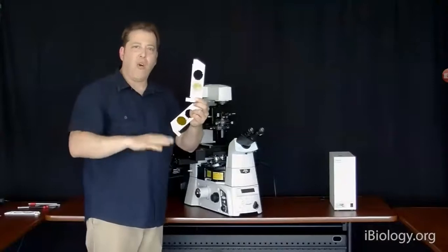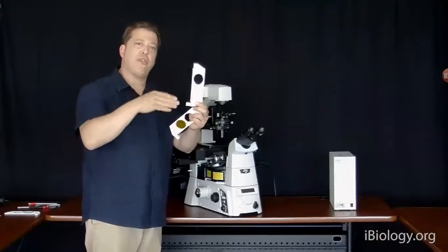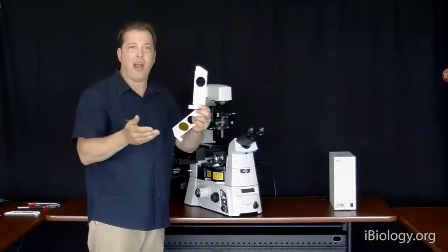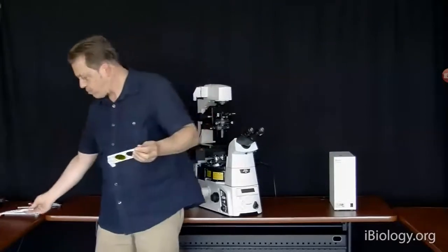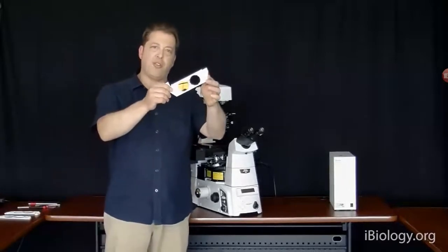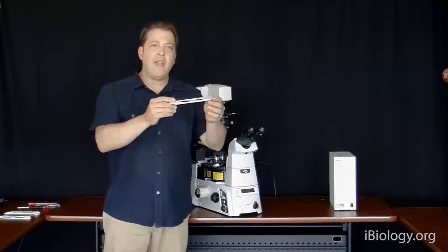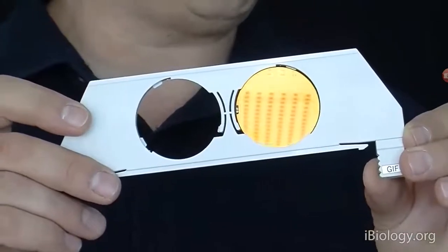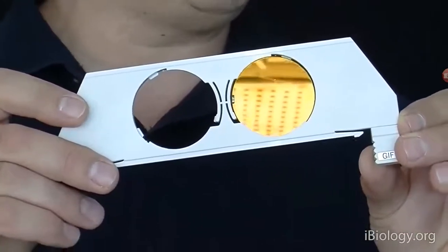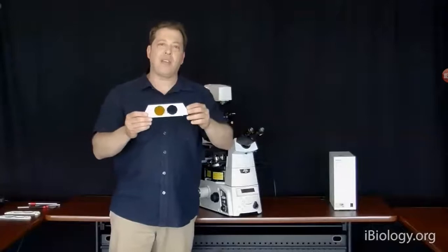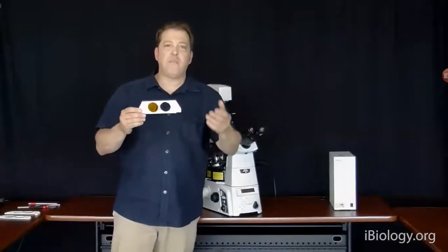And what that does is, when the halogen bulb runs at low voltage, it is more reddish, more orangish in color. The neutral color balancing filter will give you a white background as if you're running the bulb at higher voltage when it puts out more white light. And then we have a green interference filter, which is a narrowband green filter that is used for contrasting techniques like differential interference contrast or phase contrast to give you sharper resolution in those contrasting techniques by narrowing the band of wavelengths that you're using to illuminate your specimen.